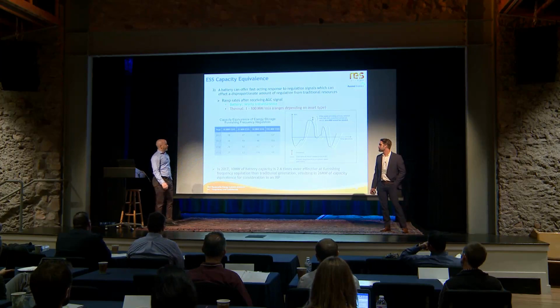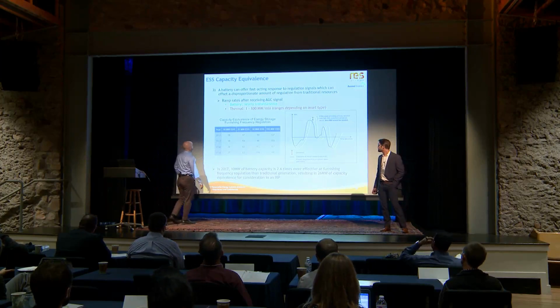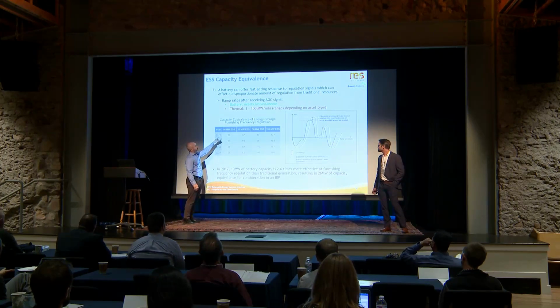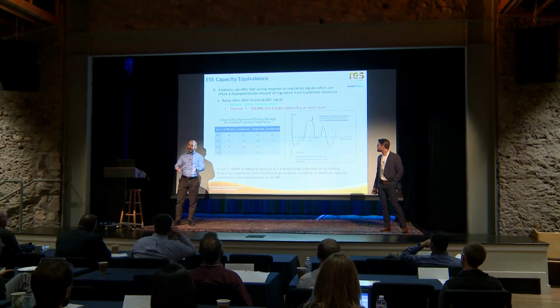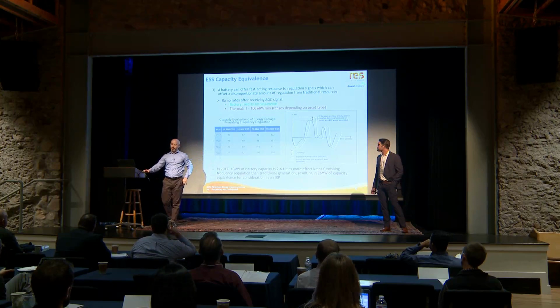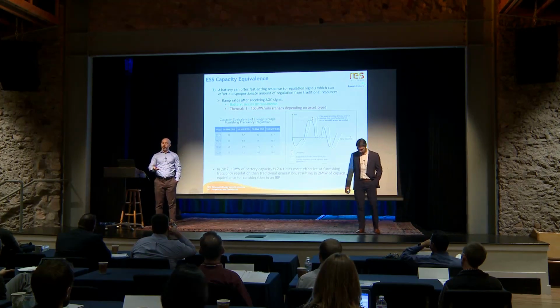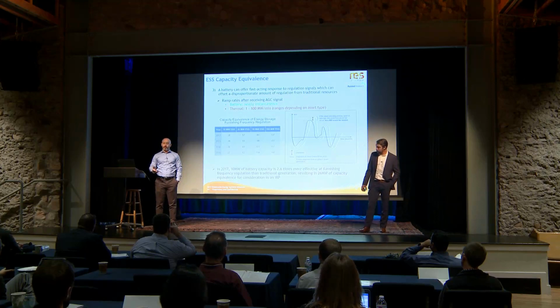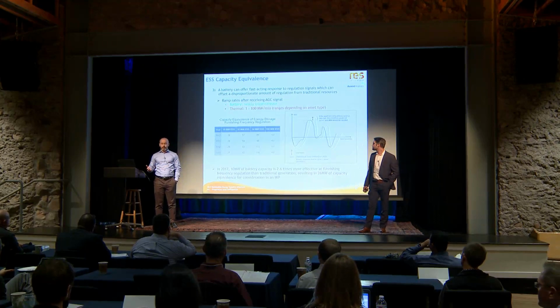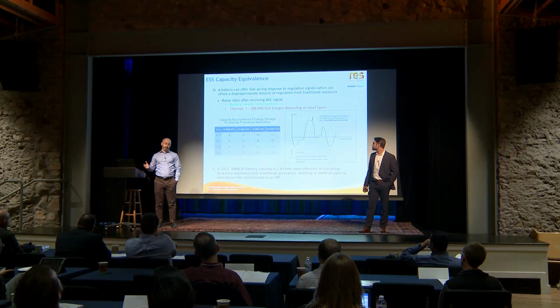Another study we looked at from another utility came up with capacity equivalents of energy storage furnishing frequency regulation. If we put a battery into our regulation-up requirement, it's worth a disproportionate amount more than its size. If I put a 10 megawatt battery in, it has a multiplier of 2.6 in this case—it's worth 26 megawatts of regulation because it can operate more quickly and target the signal more accurately. I don't need all 26 megawatts, I just needed that 10.